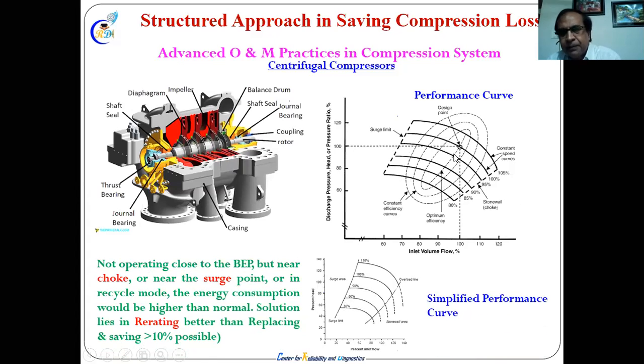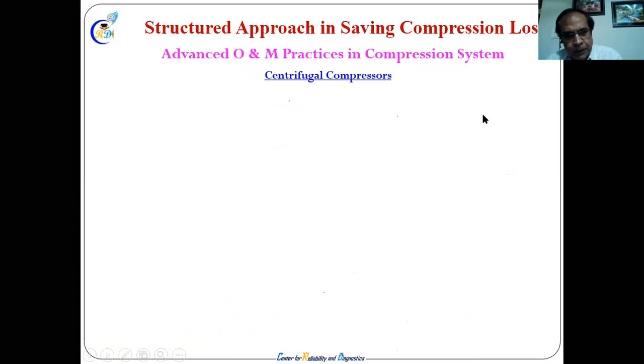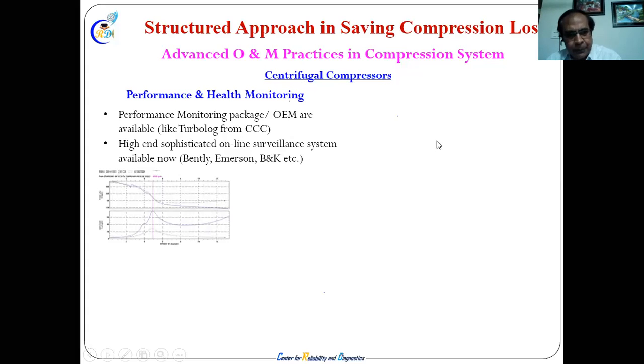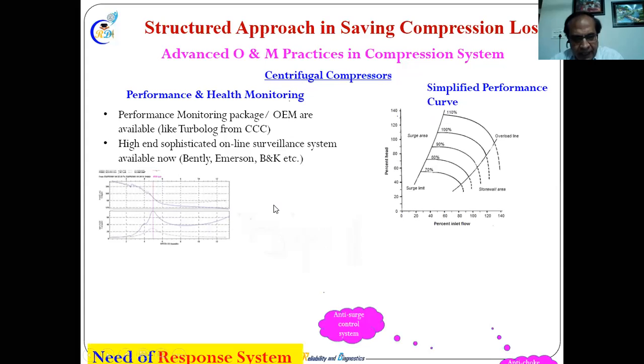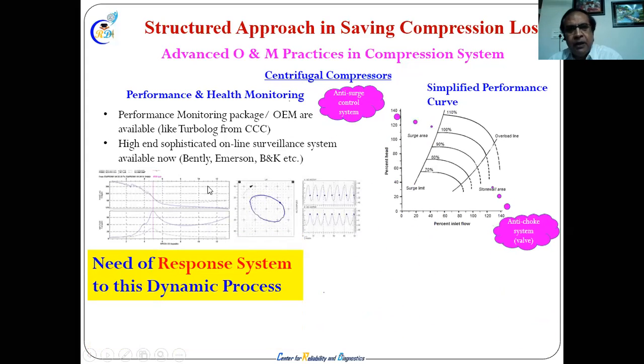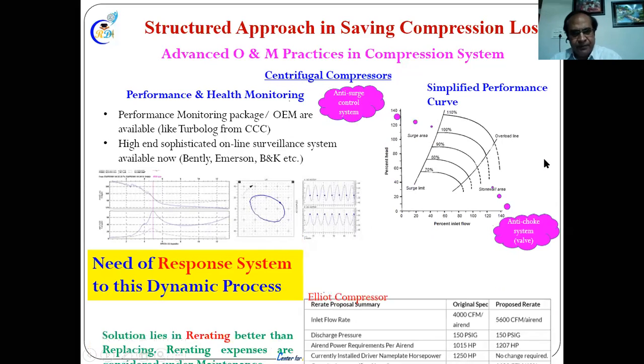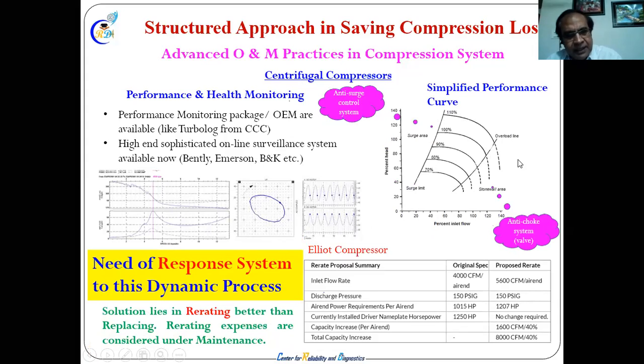This is the surge line. So this is something potentially possible, with performance monitoring and health monitoring of the centrifugal compressor. Online systems, online data and online knowledge are available, and highly sophisticated maintenance systems are available. We need to respond to the system. Just as the systems respond accordingly, we also have to respond, taking care that the centrifugal compressor is going out of the surge line and out of stonewalling. That is what we have to look into in maintenance.